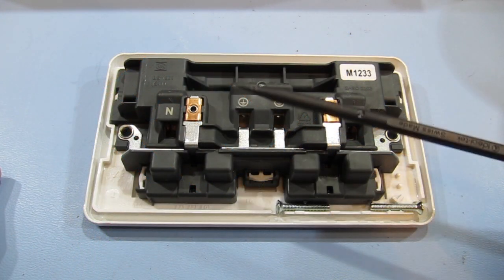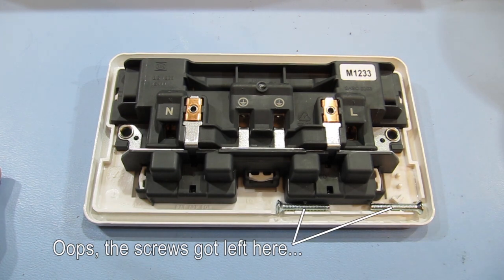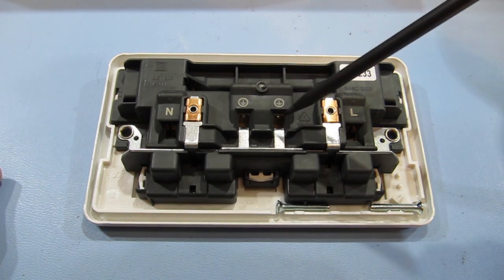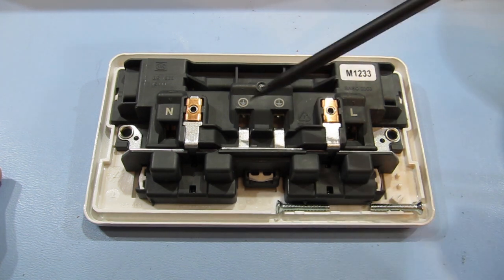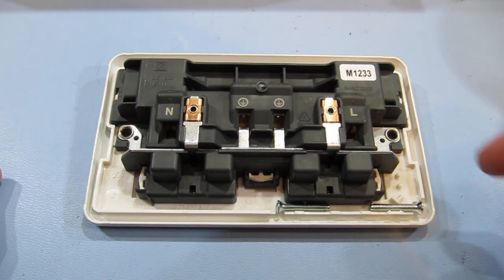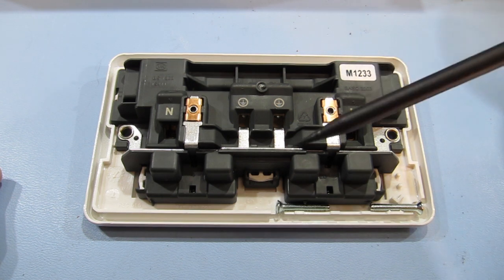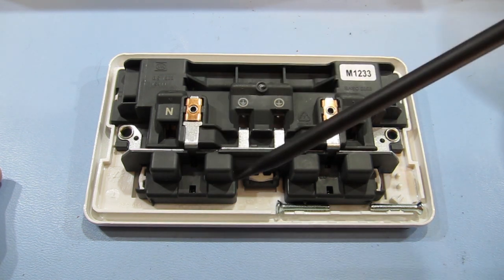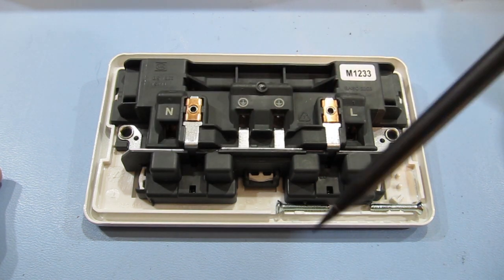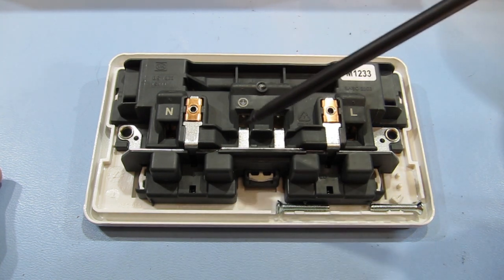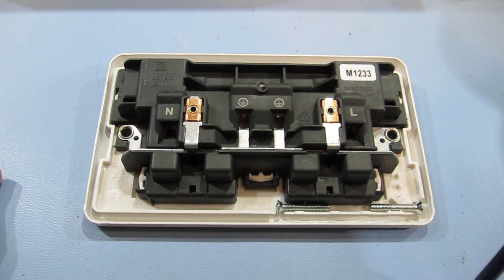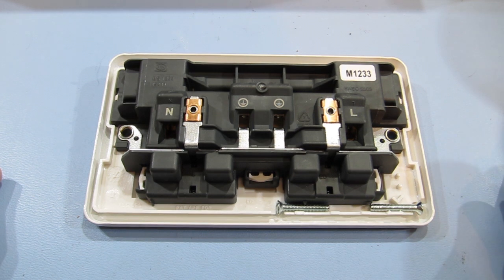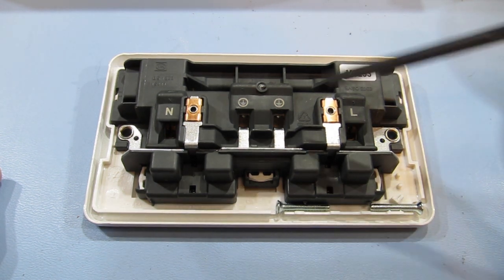So this is the back of the 13 amp socket which I'm planning on mounting to the top of the transformer. And you can see we've got the 2 earth terminals here. We have 2 just in case the socket's going to be used in an application that needs high integrity earthing. So that's typically IT environments where there's a relatively high earth current all the time from the leakage through the filters on the switch mode power supplies.